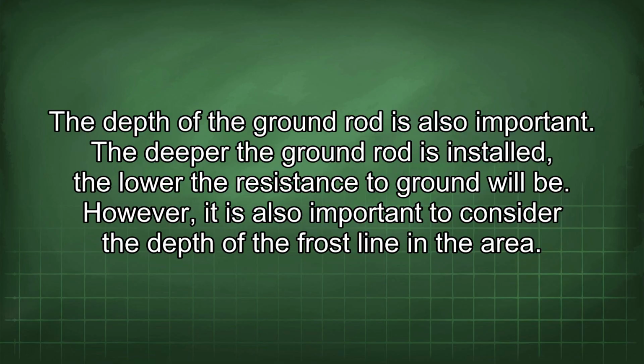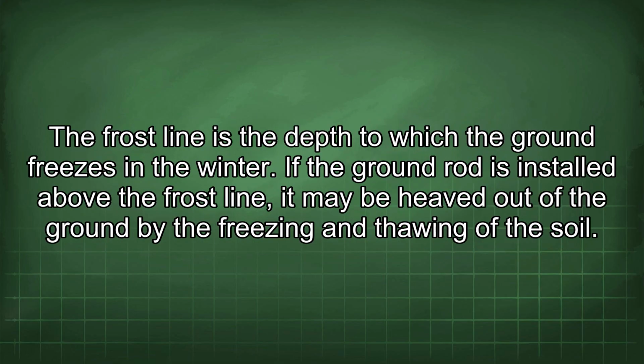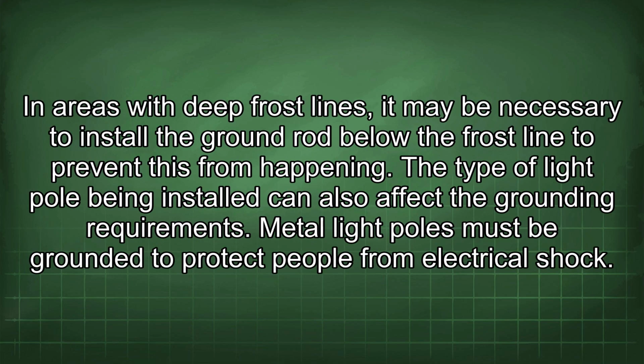However, it is also important to consider the depth of the frost line in the area. The frost line is the depth to which the ground freezes in the winter. If the ground rod is installed above the frost line, it may be heaved out of the ground by the freezing and thawing of the soil. In areas with deep frost lines, it may be necessary to install the ground rod below the frost line to prevent this from happening. The type of light pole being installed can also affect the grounding requirements.